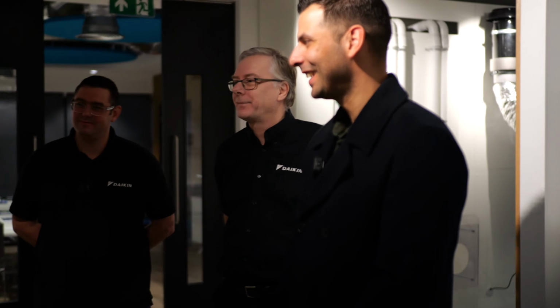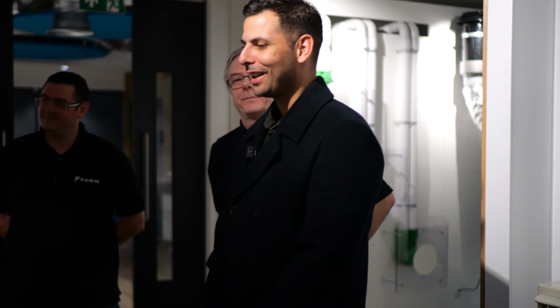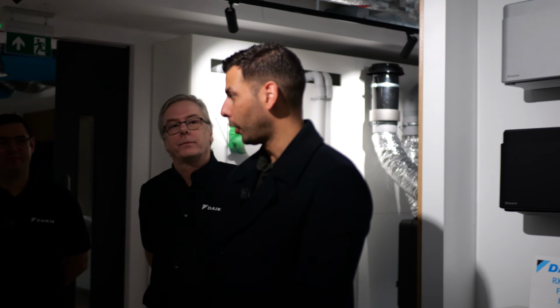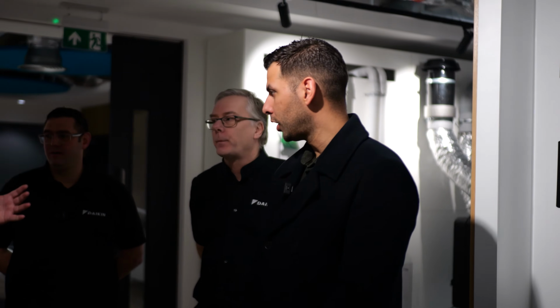Using weather compensation - that's the dark side of heat pumps. Well, it was. Now it's becoming the norm, eliminating the buffer and just having a primary, using the whole system with no TRVs. That seems to be where the higher SCOPs are coming from these days. Yes and no - that might be another conversation.